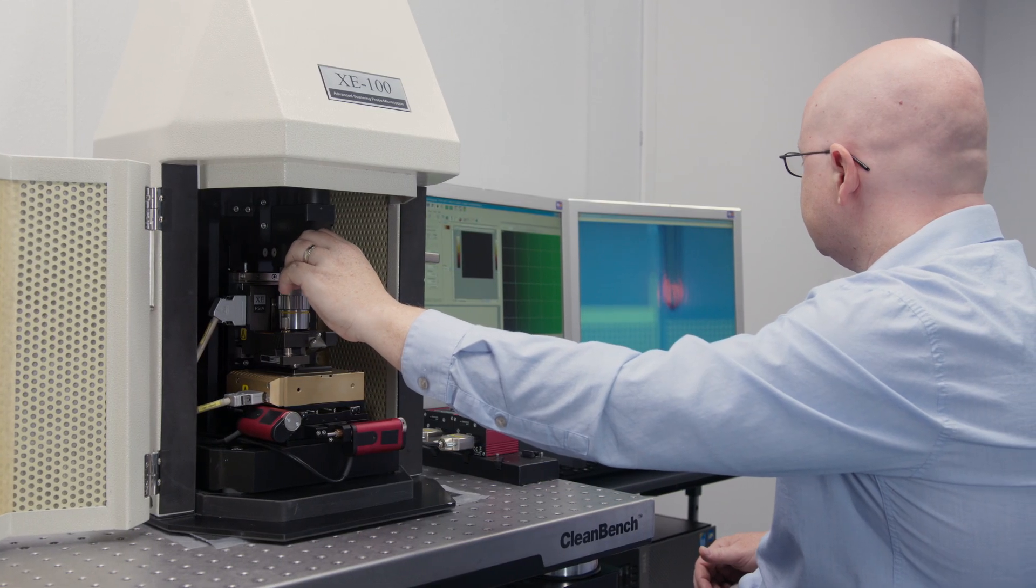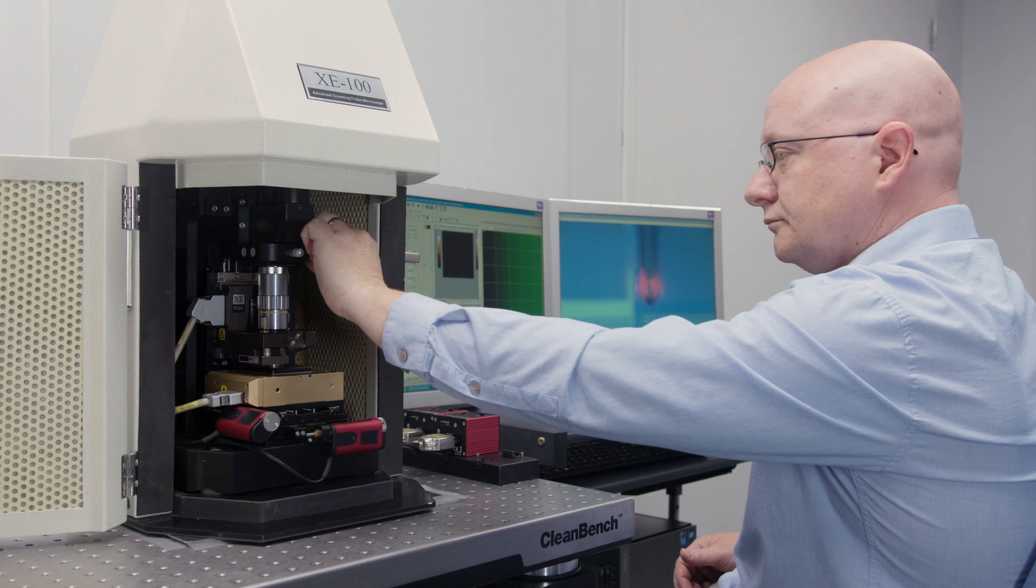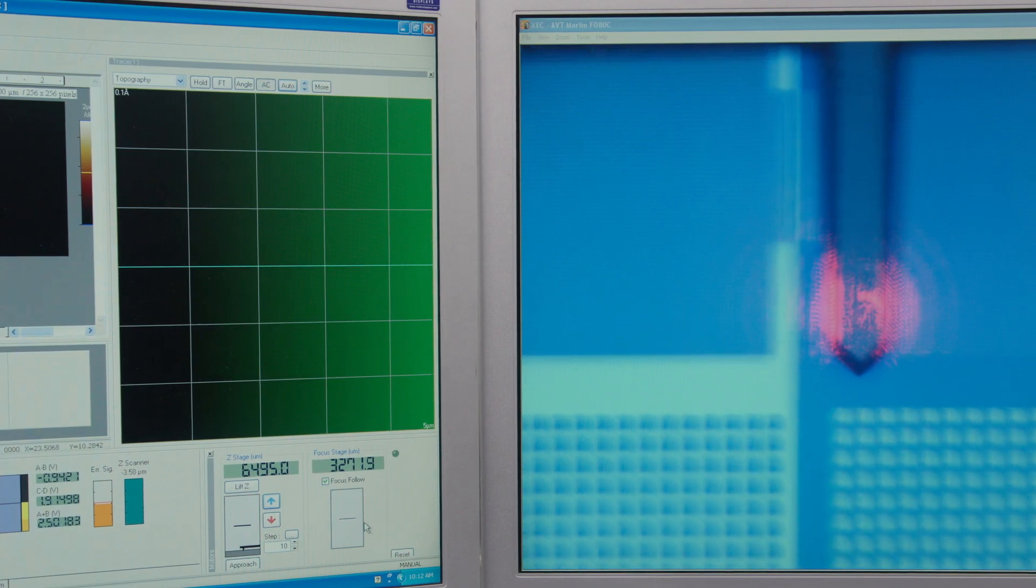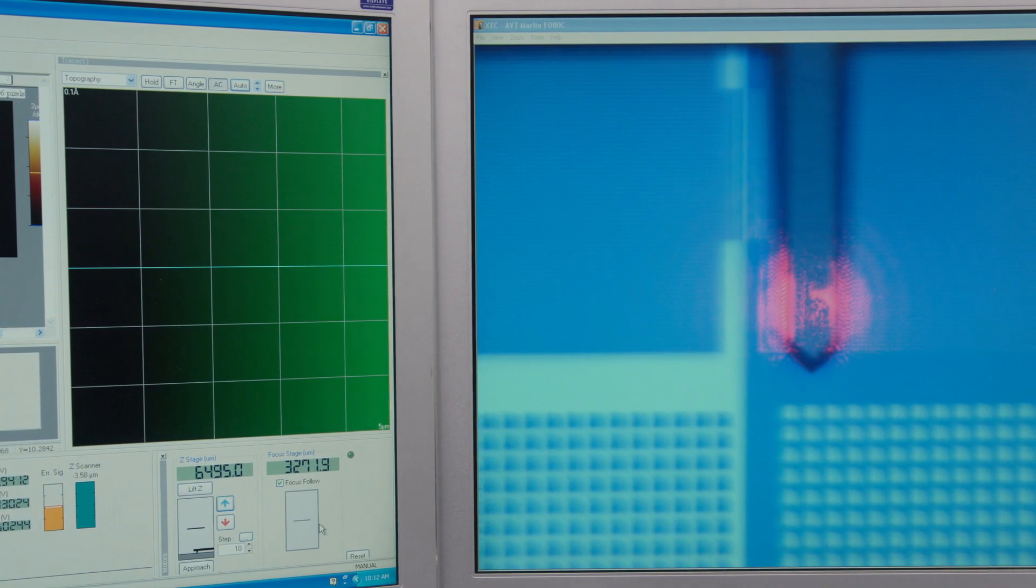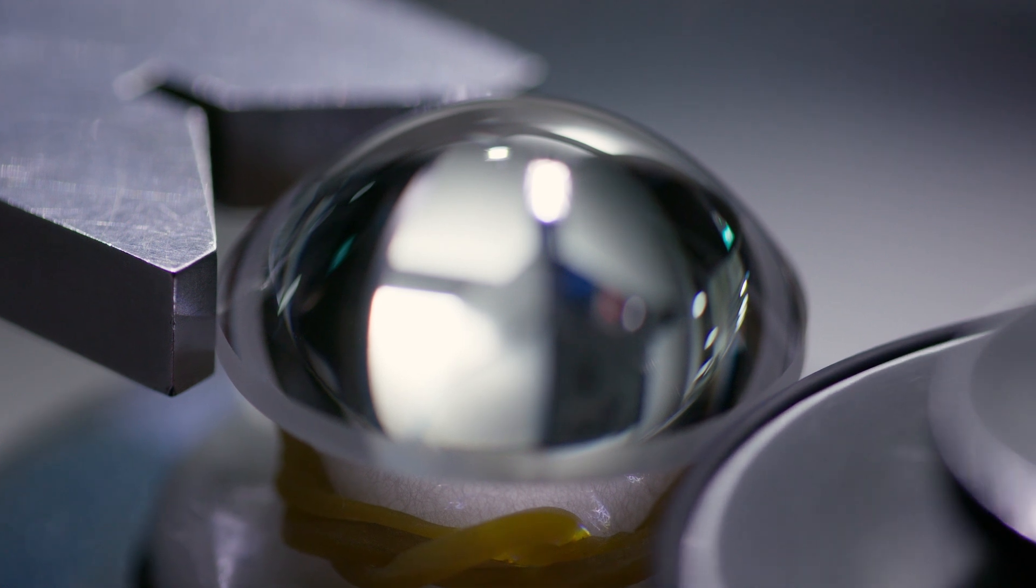Edmund utilizes many other metrology techniques, including atomic force microscopes for surface roughness, centration measurement machines for lens alignment, and autocollimators for angle verification.